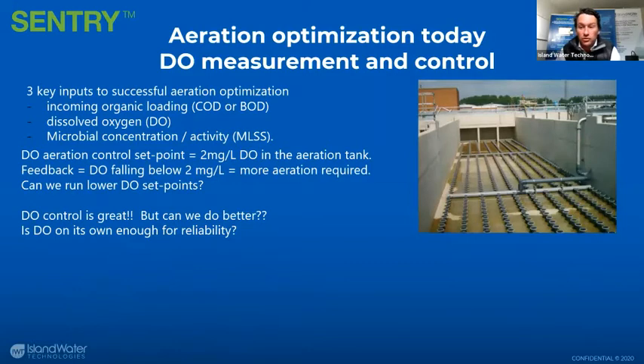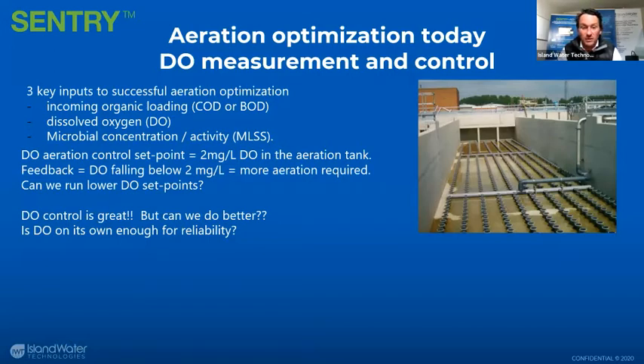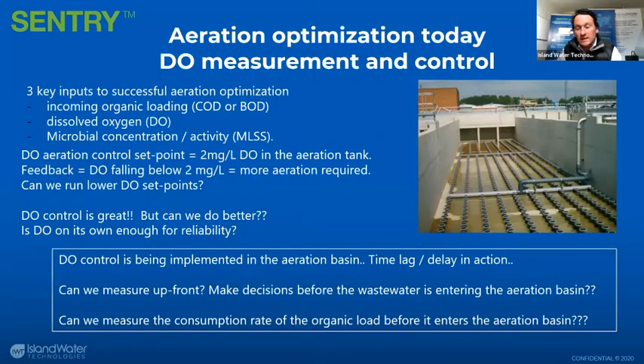When optimizing aeration, there are three key pieces of information we want. First, we want to understand the incoming organic load — how much food is available for the biomass, ideally in real time and before it even hits the bioreactor. Second, yes, you want to understand your DO — how much DO you're providing to your bioreactors. The two milligrams per liter metric is nice; above that, oxygen really isn't limiting for the biomass. But it would be interesting to look at lower DO set points to save energy. The question is: can we complement DO with other data sets?